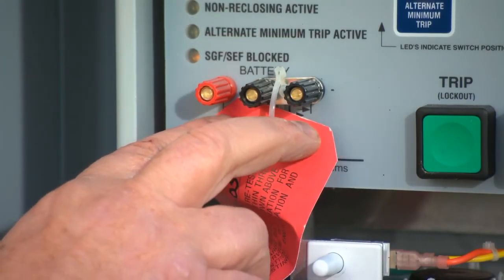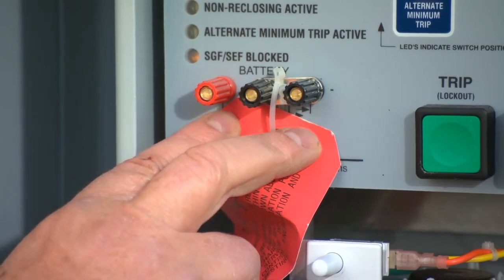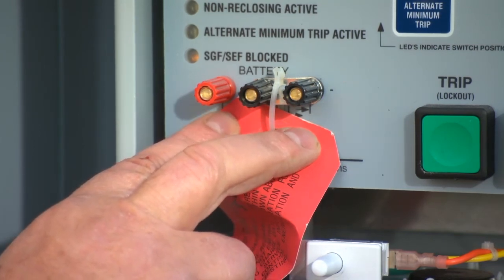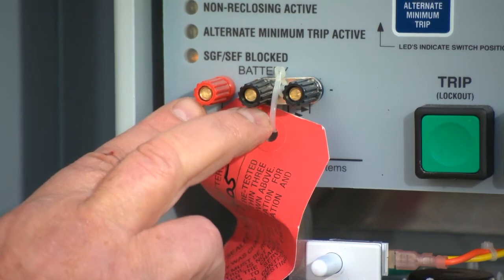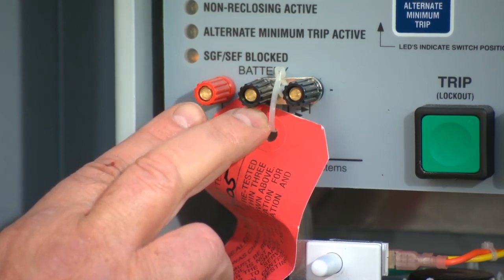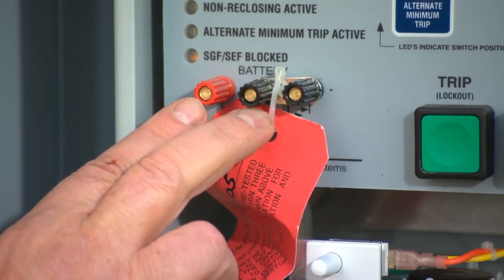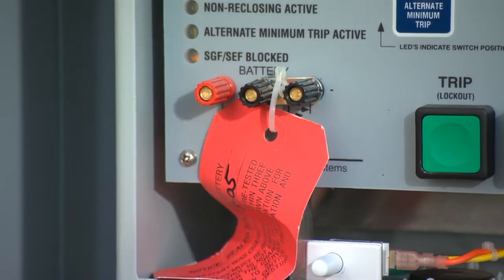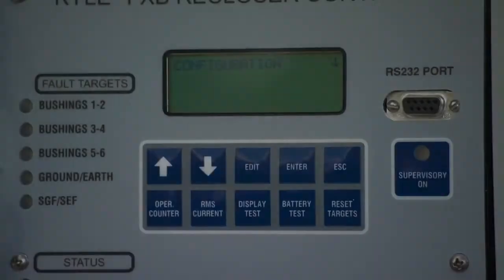Looking more closely across the bottom of the unit are the battery test terminals. A load test or voltage test may be applied to these terminals to determine the current idle voltage of the batteries. This is achieved by applying a voltmeter between these 2 terminals.